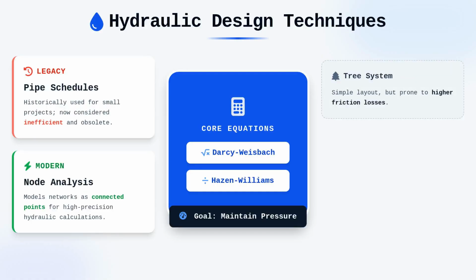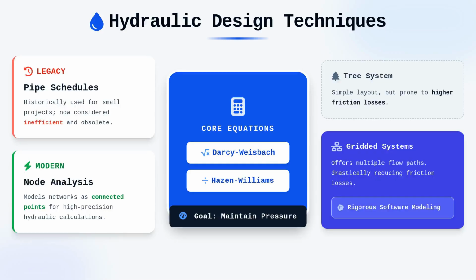Whether you are designing a tree, grid, or looped system, the objective is to ensure that the piping layout maintains the required pressure at every sprinkler head. Gridded systems, in particular, offer efficient water routing by providing multiple flow paths, which reduces friction losses significantly compared to tree systems. However, this complexity requires greater rigor in hydraulic software modeling to ensure that the water delivery is uniform across the entire design area.